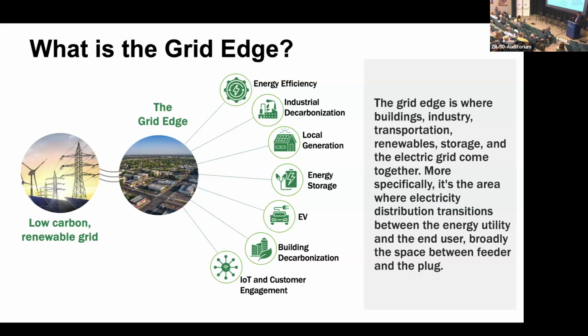Why is it important? If you're working on customer technologies like 120-volt heat pumps or smart panels, that automatically reduces the amount of infrastructure you have to put on the electrical side. For example, we were talking to home builders last week, and one of their pain points is that they cannot get enough transformers. When you go to all-electric construction, they're concerned they'll need more transformers—where they used to put in one, they now need three, and there's a supply challenge. So if you can figure out how not to increase the panel size of the building, that automatically means fewer transformers, fewer upgrades on feeders, fewer upgrades in substations, and reduces costs overall. That's a big focus area for us.